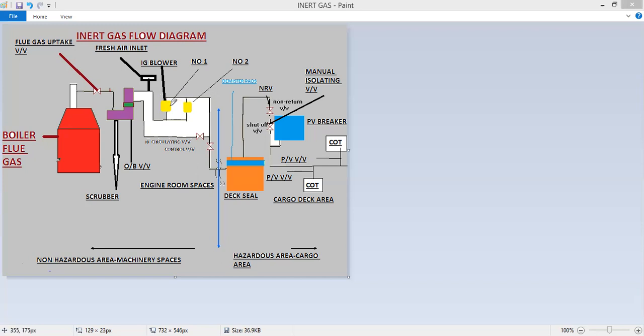Now the blowers have specific requirements. The capacity of blowers, either of one or either of two combined, should be more than 125% of the maximum discharge rate of the vessel. The vessel can have one blower or two blowers. If the vessel has one blower, then it is supposed to have 100% spare for that blower. It might have two blowers. If they are of a different capacity, not up to the requirements, then both are supposed to have 100% spare. And if one of them or each one of them meets the requirements, then the spare parts are not required because there are two blowers.